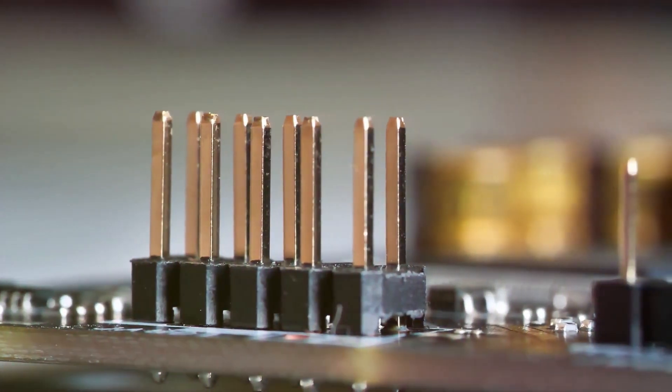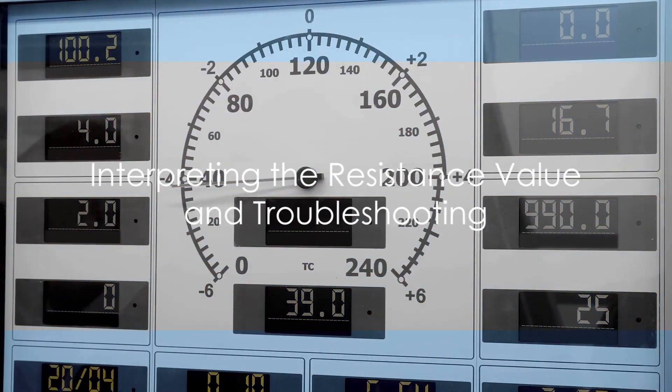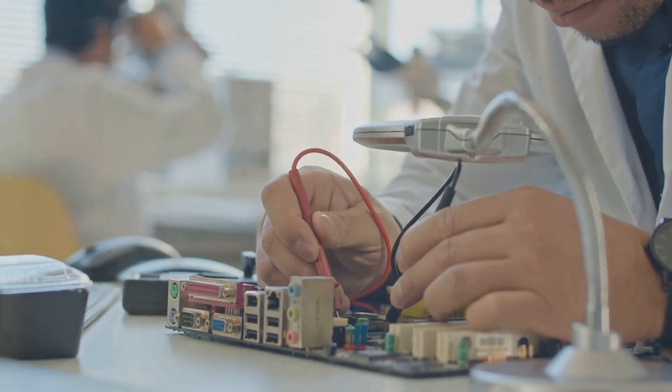With the resistance value recorded, let's interpret what it means. The resistance value you obtained should be within a specified range provided by the solenoid manufacturer. This range is indicative of a healthy solenoid coil. If the resistance is within this range, it's a green light. Your coil is functioning properly.